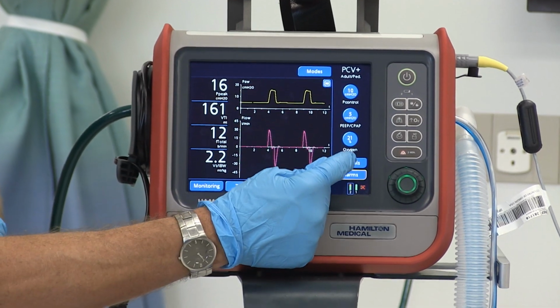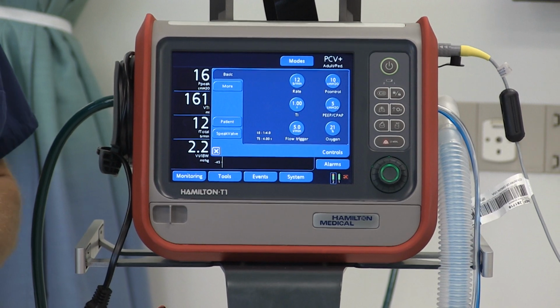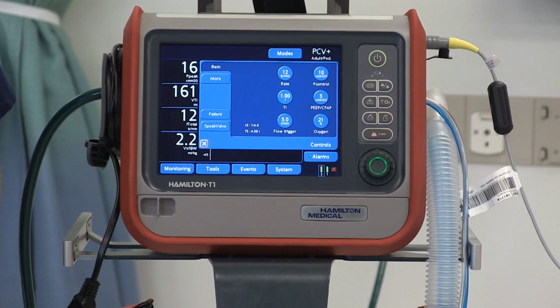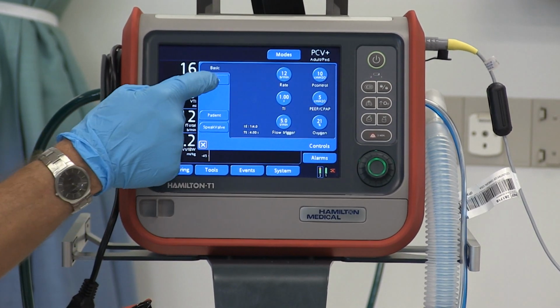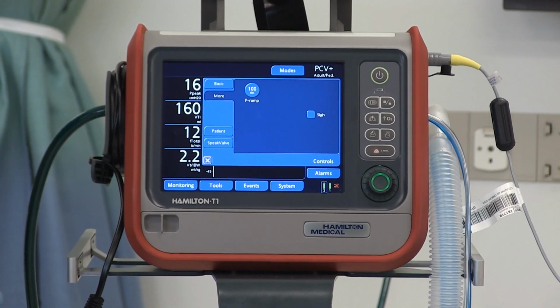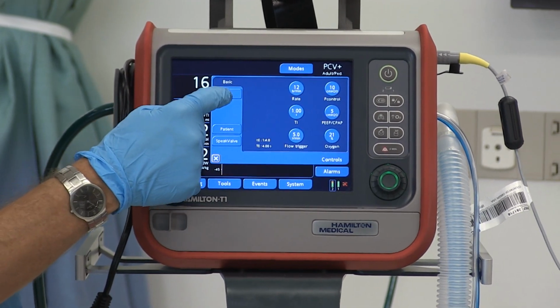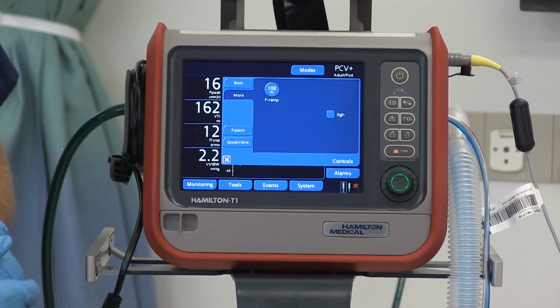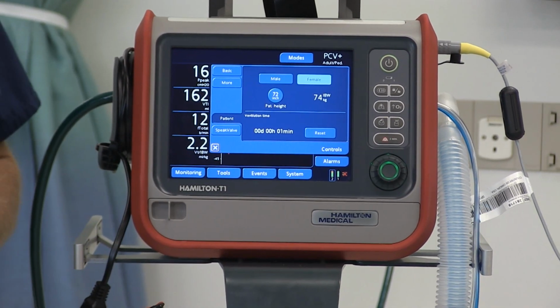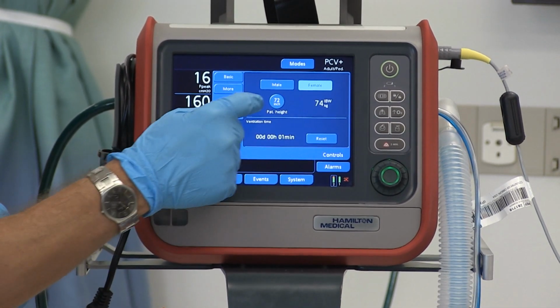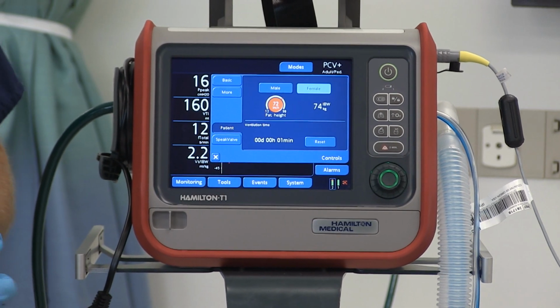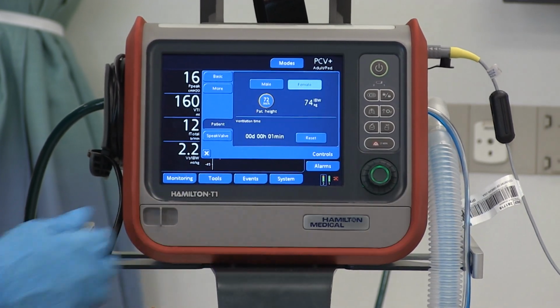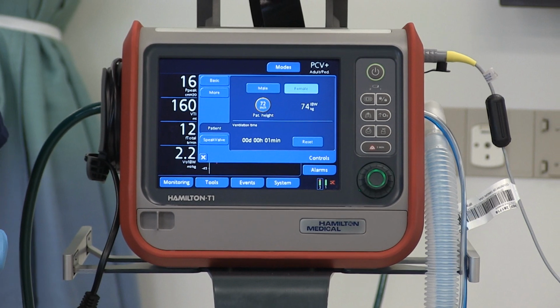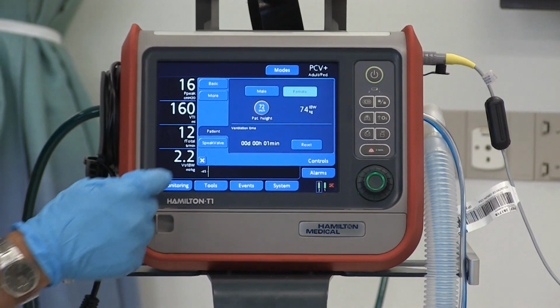To see all the controls, touch the Controls tab, and all the controls are available here. There's two tabs in the controls. We have the basic settings and the secondary settings. And below that, there's a patient tab where we can adjust the patient information if we decide that we had it in incorrectly, or we just want to double check the patient size and make sure we have the right ideal body weight on the ventilator.